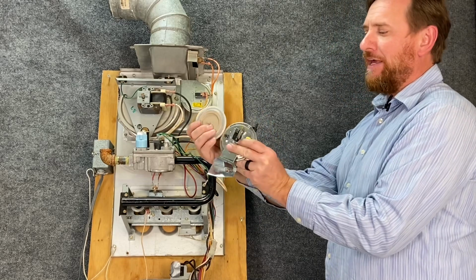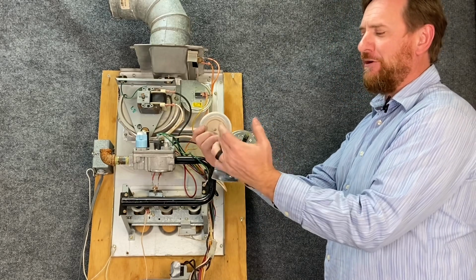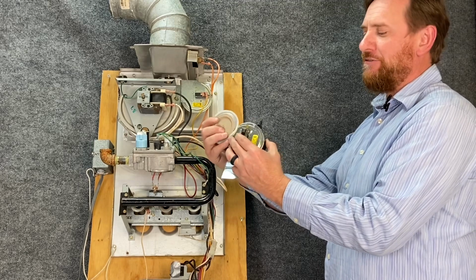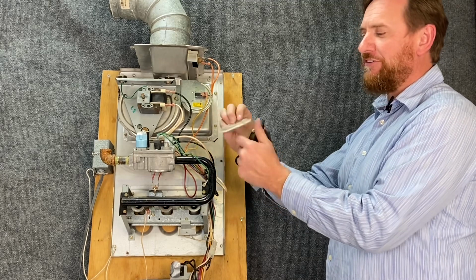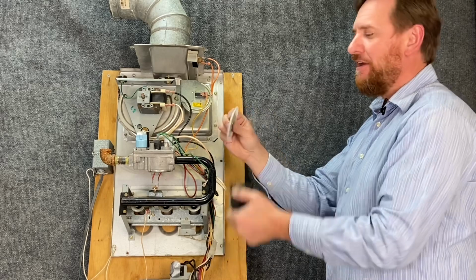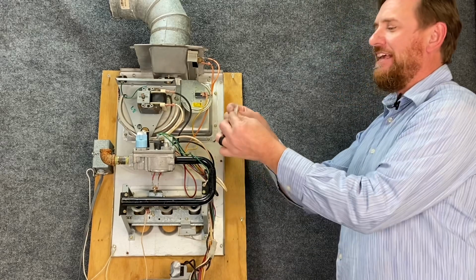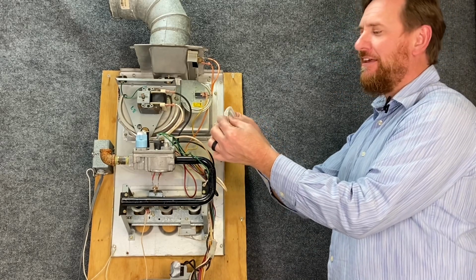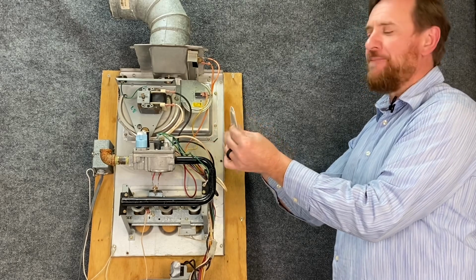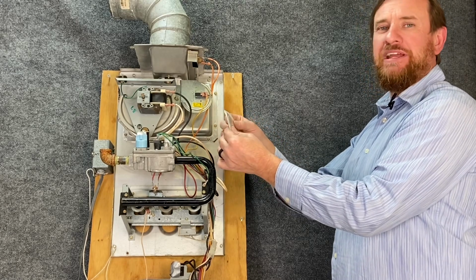So when we pull a pressure difference on one side, the atmospheric pressure pushes on the other. What it does is make the switch close. It physically moves the contact with this piece here. But if we see, this diaphragm fitting is very fragile. It's a very thin type of material, so it's very easy to break. Over time, they can break or get worn out.